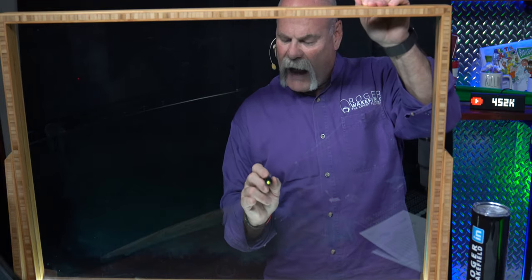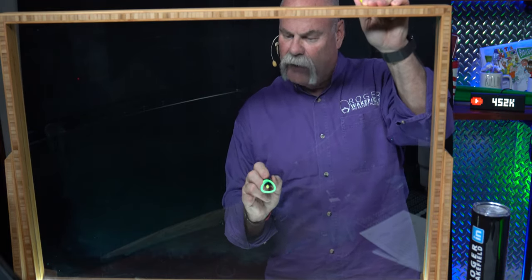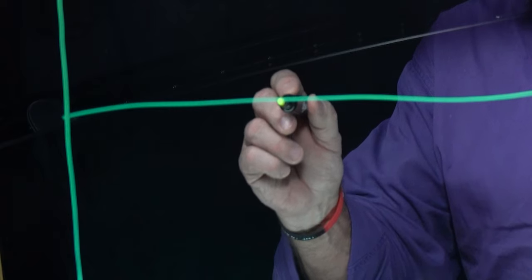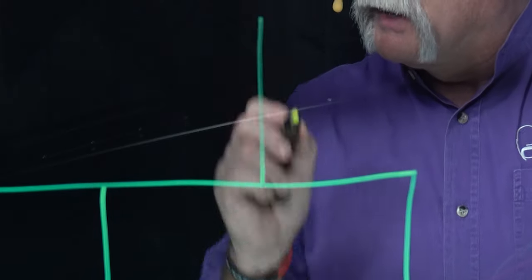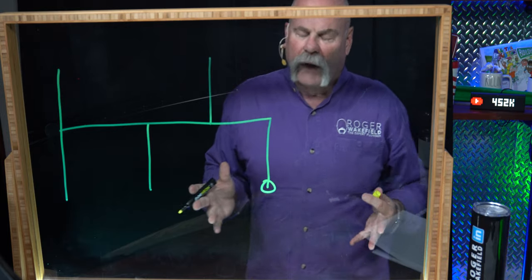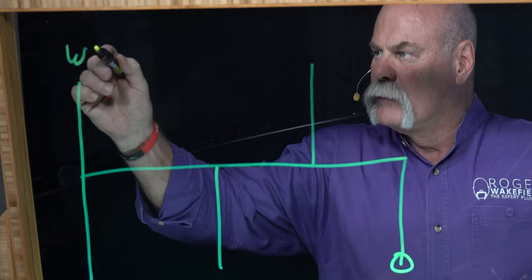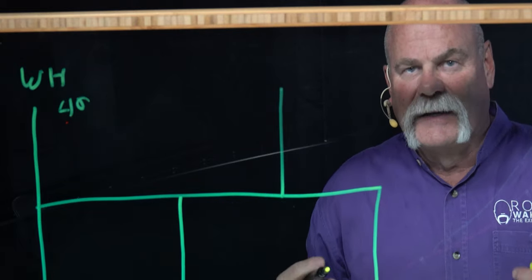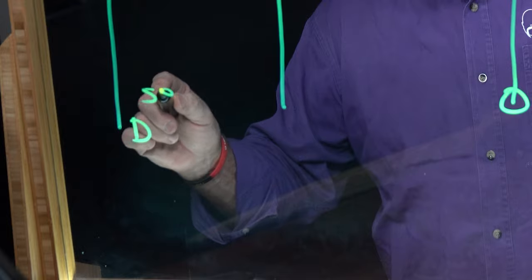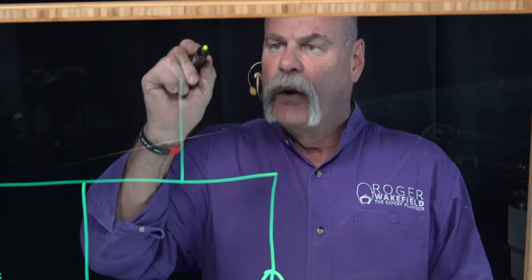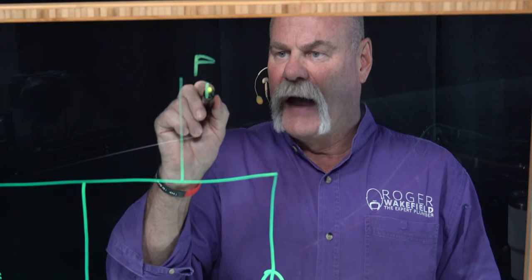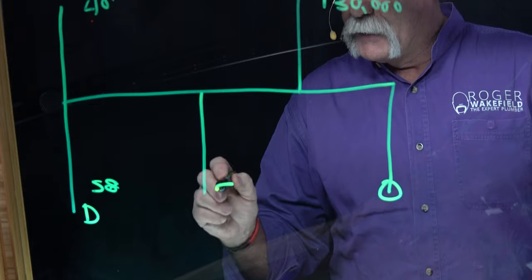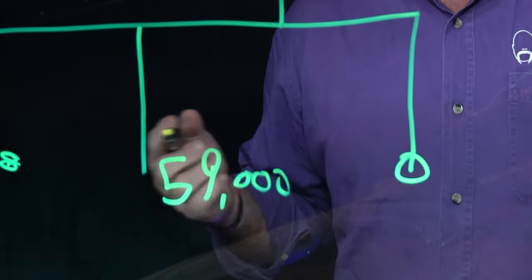I'm going to do a really simple drawing. I'll put the meter right here at the house, come up, go down, bullhead it at the end, and put a branch coming off here and another branch coming off here. We're going to assume the water heater is 40,000 BTUs, a dryer at 28,000 BTUs, a furnace at 130,000 BTUs, and a kitchen stovetop at 59,000 BTUs.